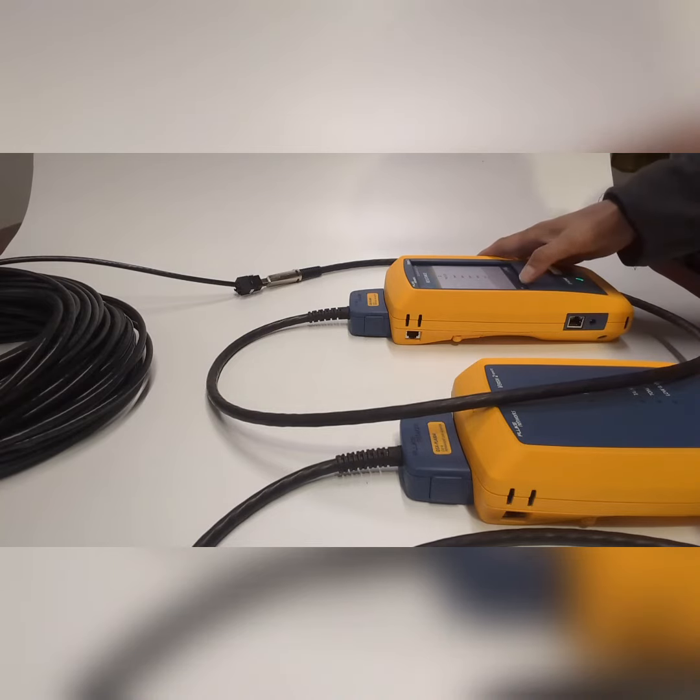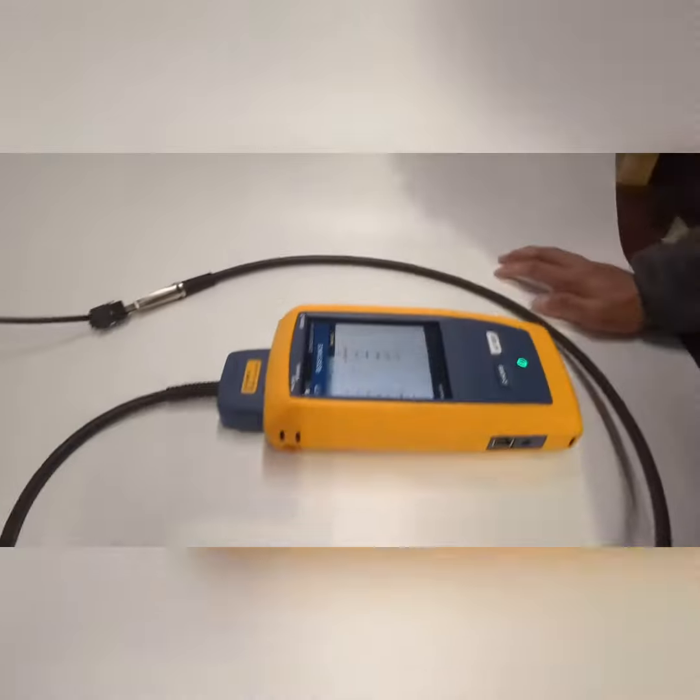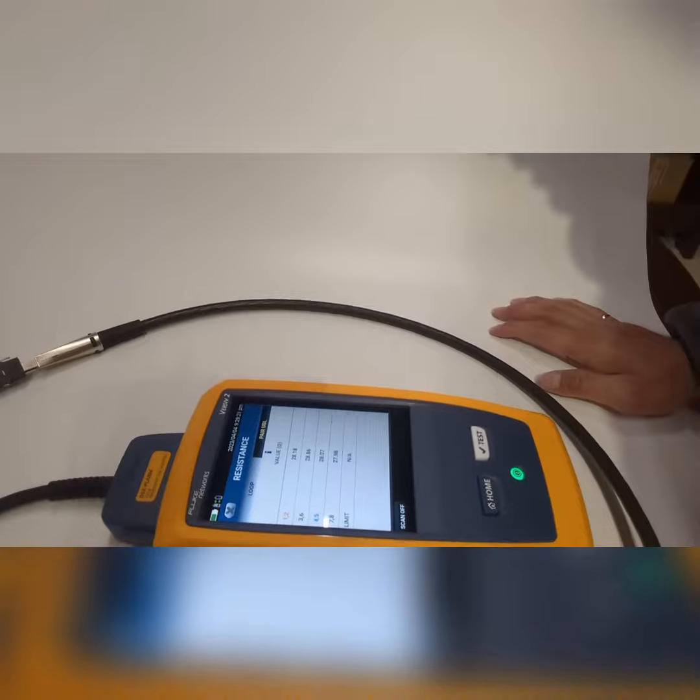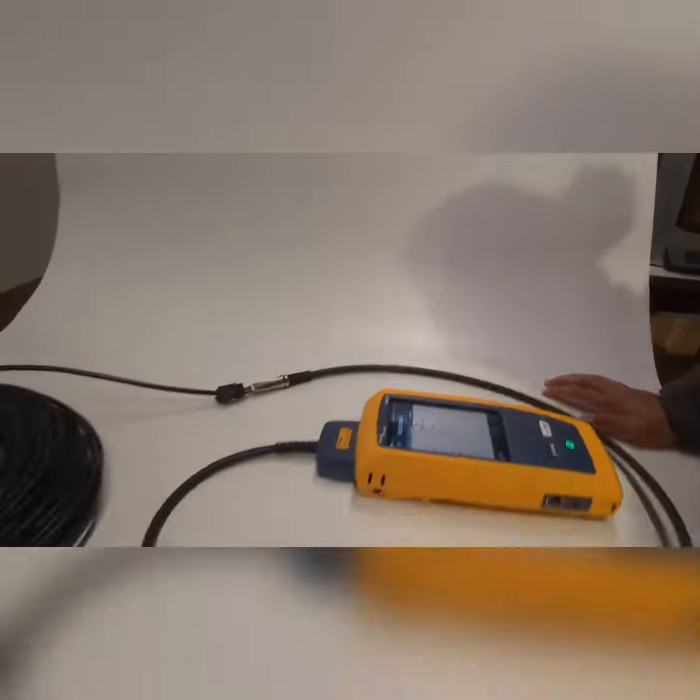Now we're testing a longer spool of CCA cable. Again, let's scan it with a Fluke tester. You can see the DC resistance value is about 28 ohms.